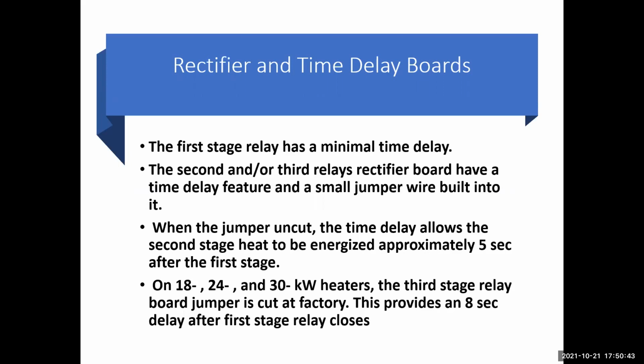The second and third relay boards have time delay features and a small jumper built into them. When the jumper is uncut, the time delay allows the second stage to energize in approximately 5 seconds after the first stage. On 18, 24, and 30 kW heaters, the third stage relay board jumper is cut at the factory, and that provides an 8-second time delay from the first stage relay closing. So your second stage has a 5-second time delay. Third stage has an 8-second time delay.